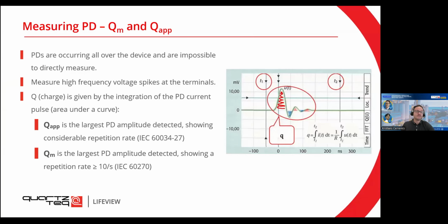Now the question, I think, is how do we actually monitor? Because we have different types of machines, different setups, and different environments for these machines. So there needs to be a way to detect these partial discharges. And they are happening all over the machine, so it's impossible to directly measure or capture one particular discharge. Instead, we can use different types of methods. You can have chemical methods, optical methods, acoustic methods. Each of these has its own cons and pros, and one of the most widely used is an electrical method. So what we do is we measure high frequency voltage spikes at the terminals of the machine. They look something like the graph on the right, where the voltage spikes up.